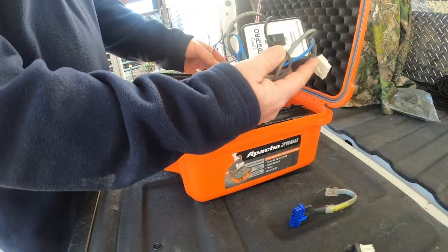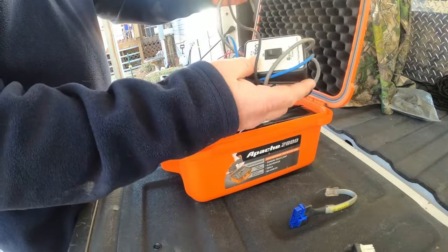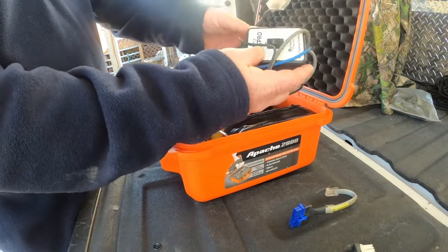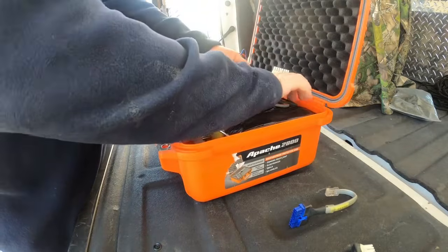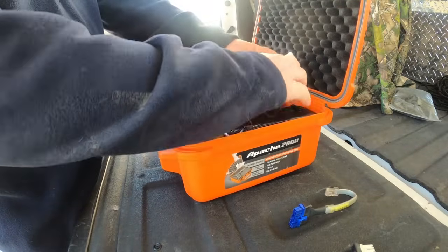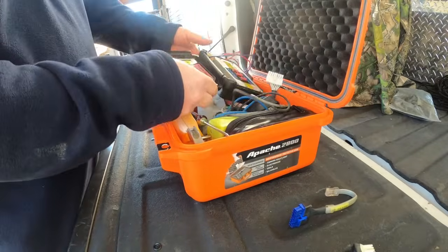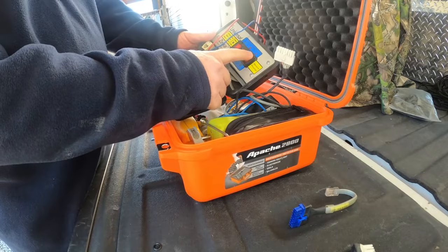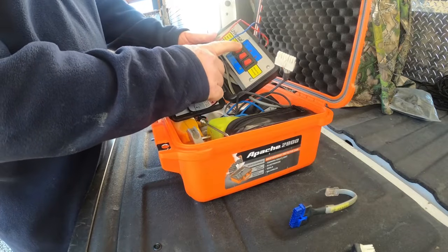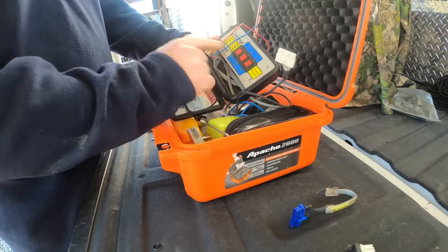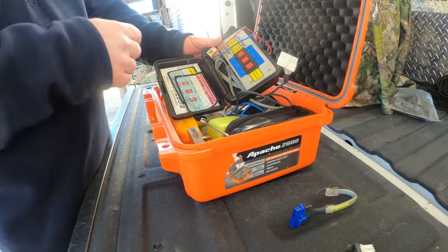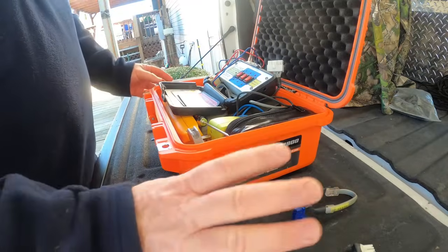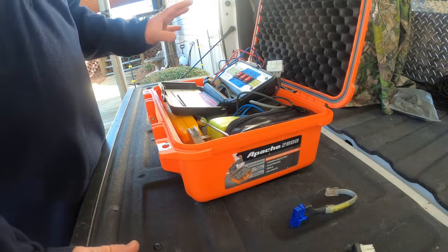You can get the TechMate Pro. This is an older version, just comes with the 16 pin adapter for the 16 pin variable speed motors. I have that, but basically it's just kind of an on and off, whereas with this I can run different speeds: high, low, medium, cooling speeds, heating speeds, fan, constant airflow for your continuous fan, and it'll test that motor, determine whether you've got your board problem, whether you've got a module problem.